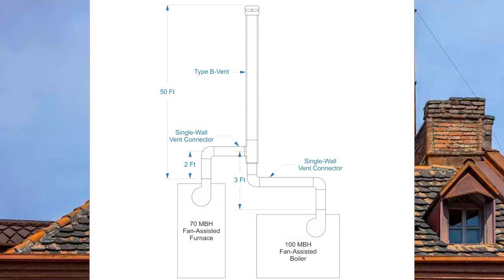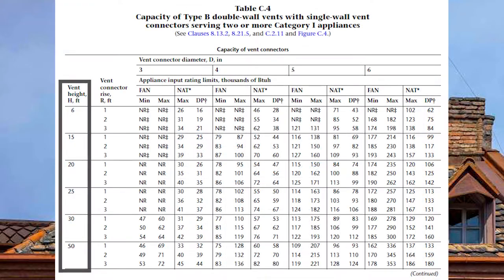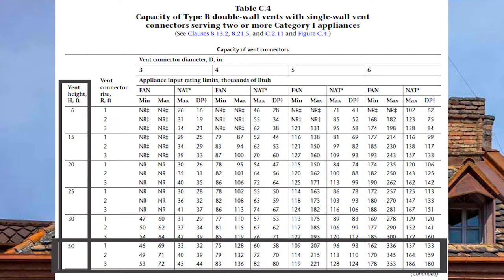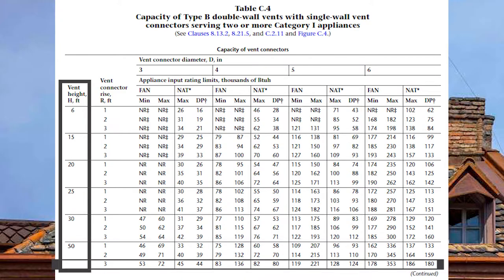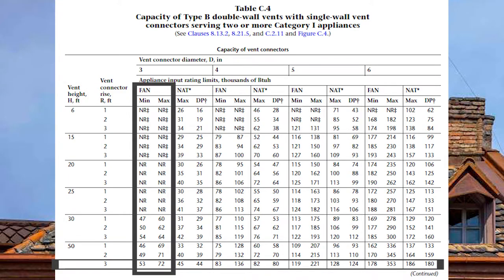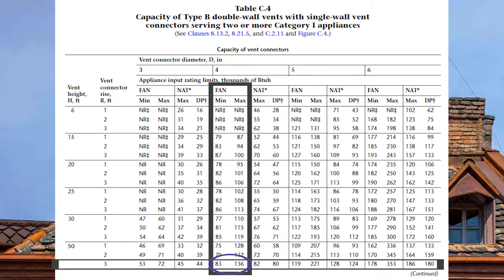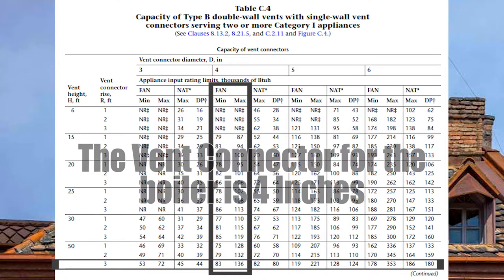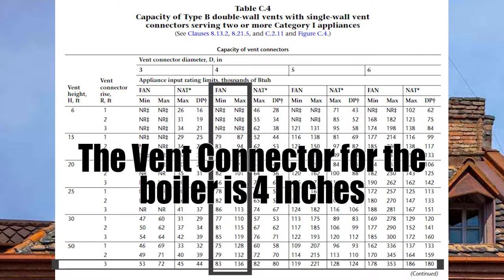Now let's take care of the boiler. Coming down to a vent height of 50 feet and across on a vent connector rise of three feet. The three-inch vent connector is only good between 53,000 and 72,000 BTUs. But the four-inch is good between 83,000 and 136,000 BTUs — perfect for my boiler. So I will have a four-inch single wall vent connector serving that boiler.